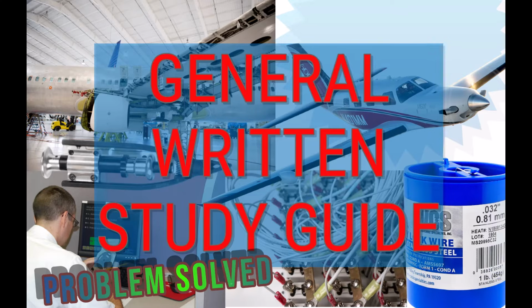If electrolyte from a lead-acid battery is spilled in the battery compartment, which procedure should be followed? Apply sodium bicarbonate solution to the affected area followed by a water rinse. Which statement regarding the hydrometer reading of a lead-acid storage battery electrolyte is true? The hydrometer reading does not require a temperature correction if the electrolyte temperature is 80 degrees Fahrenheit.